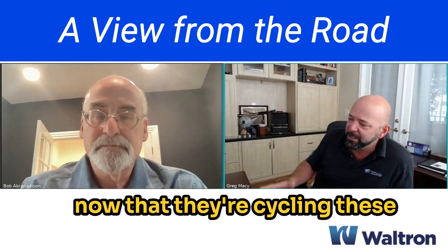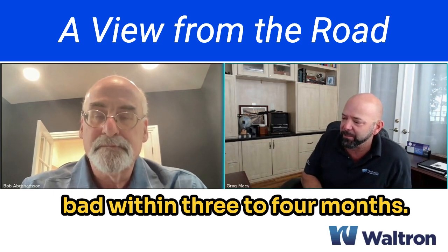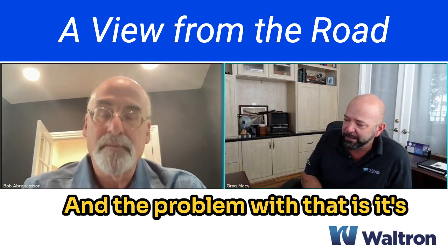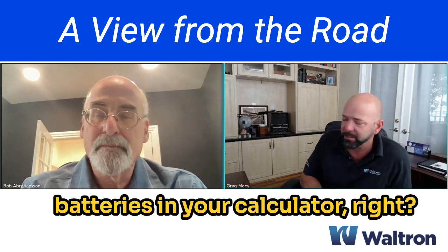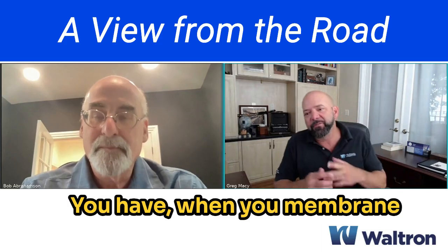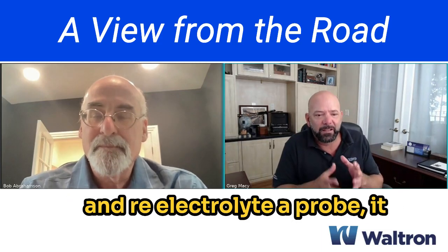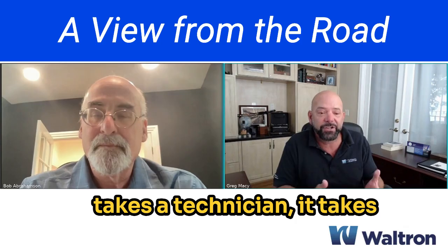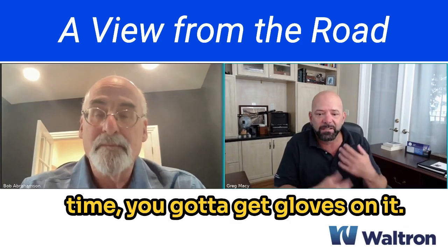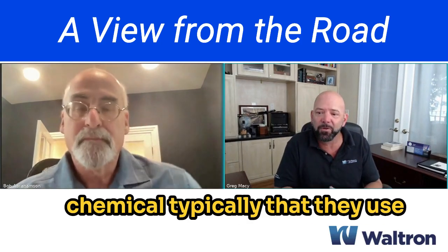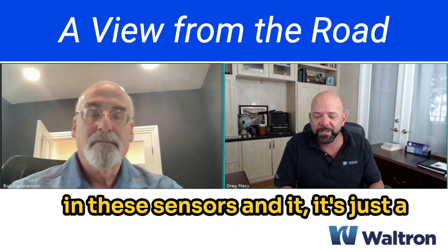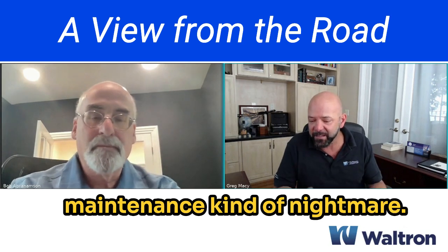And now that they're cycling, these batteries basically are going bad within 3 to 4 months. And the problem with that is it's not as simple as you changing the batteries in your calculator, right? When you remembrane and re-electrolyte a probe, it takes a technician. It takes time to get gloves on it. It's potassium hydroxide, the chemical typically used in these sensors. And it's just a maintenance kind of nightmare.